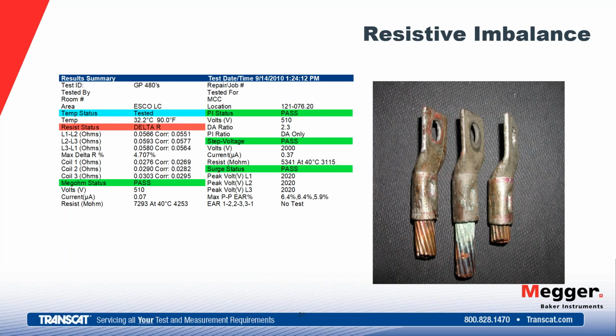Here's an example of a resistive imbalance at a paper mill. We've got a 4.7 imbalance. So they went to investigate in this particular outage and they found connections that have corrosion on them, giving a higher resistance at that point, causing a voltage imbalance and current imbalance in that motor, causing high heat. So they replaced the connections and now they put that motor back onto a better curve.